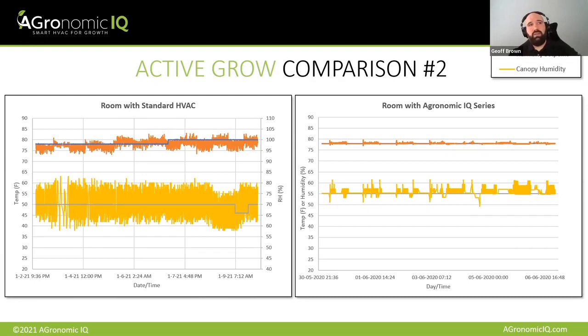And again, you can see, in this case, there's a 20% relative humidity swing in that room on the left. And we're sub 10% in the room controlled by Ag IQ. So we're controlling it in gross numbers about 50% tighter, although you can obviously see that it's a much more stable environment as well. This also has an energy impact to your facility.